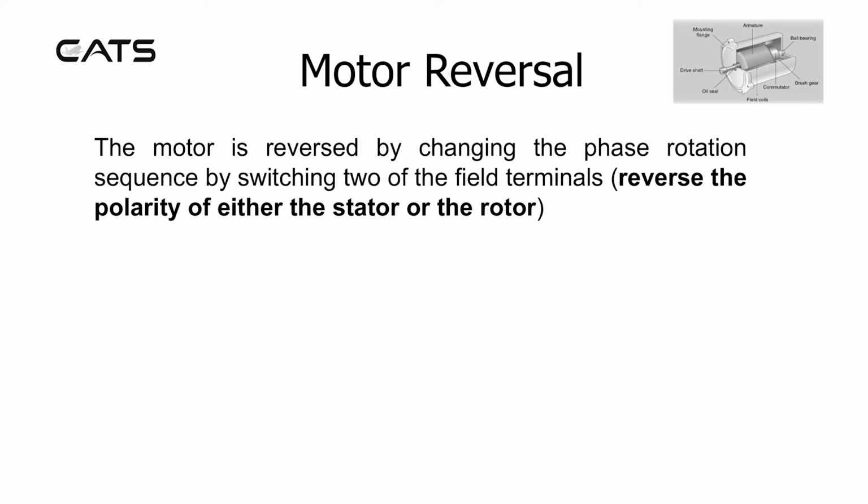Motor reversal. The motor is reversed by changing the phase rotation sequence by switching 2 of the field terminals. Reverse the polarity of either the stator or the rotor.